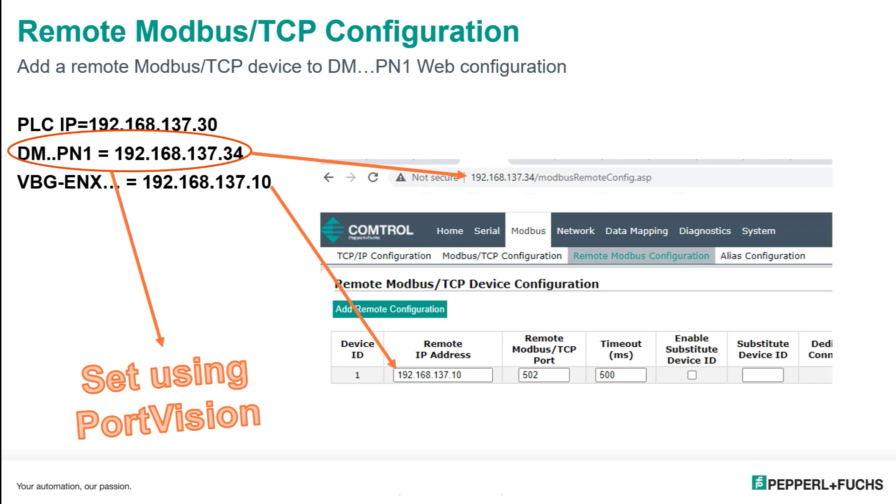When you do this, what you're going to do is set up under Modbus, Remote Modbus Configuration. This is where you're going to define the device ID and associate it to a Modbus TCP address. So I put in my IP address of my device 192.168.137.10, and I've defined it for DeviceID1.